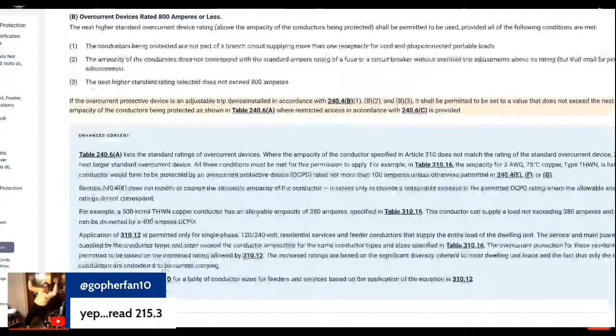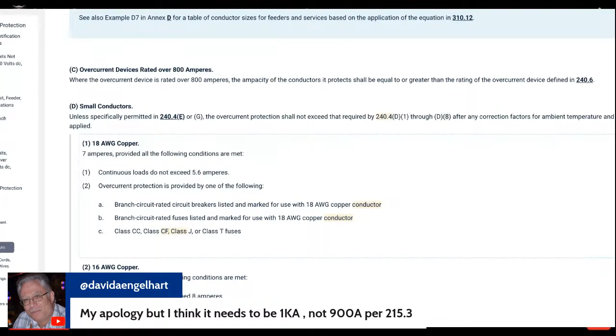How can you put it on 1,000 amps, Jeremy, if it says the overcurrent device can't exceed the ampacity of the conductors? The conductors aren't rated for 1,000 amps.